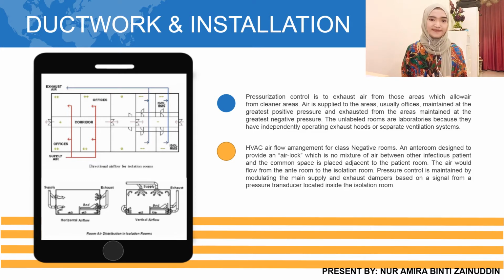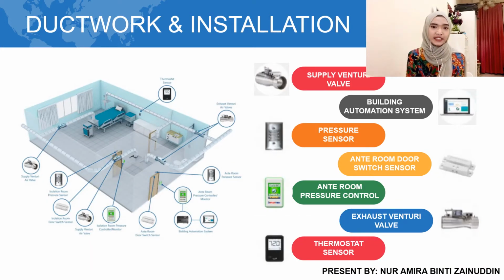Lastly, cleaner air is supplied from the anteroom and the pressure is maintained using an exhauster. Generally, the equipment used includes a supply venturi valve, pressure sensor, anteroom door switch sensor, anteroom pressure control, exhaust venturi valve, and lastly a thermostat sensor.